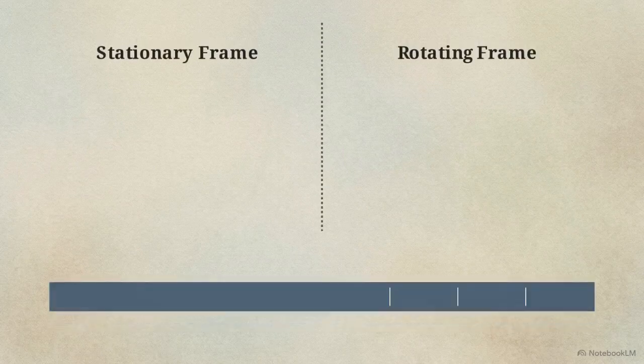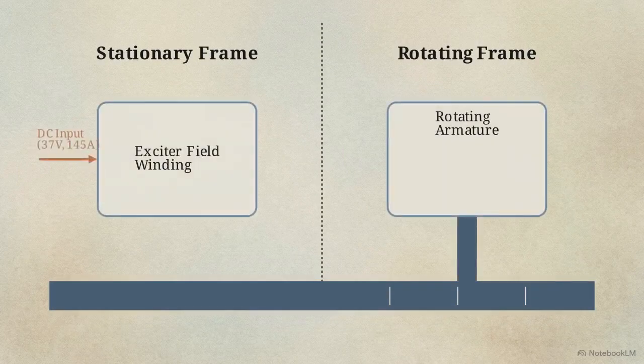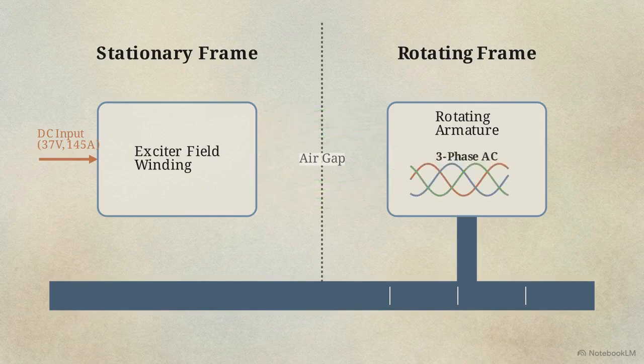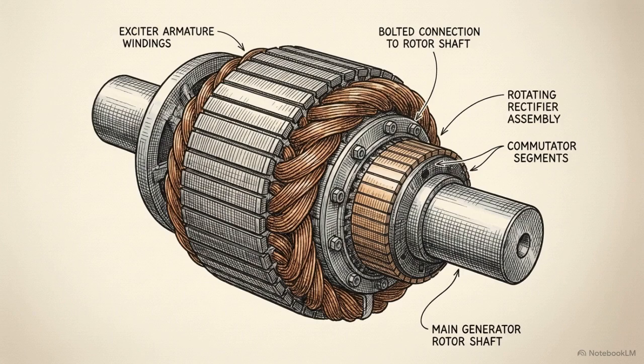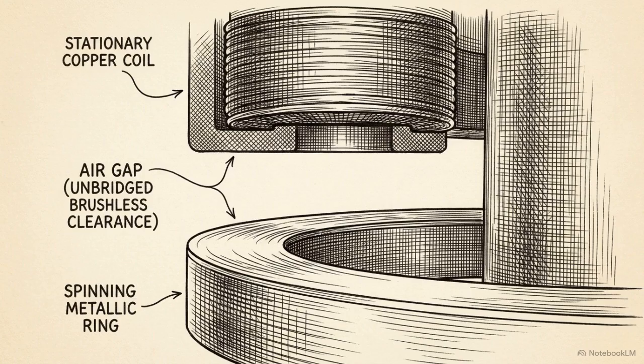This split-screen diagram maps the brushless excitation scheme using an inverted alternating current synchronous generator coupled to the main shaft. First, DC power feeds into the exciter's stationary field winding, inducing an alternating current across the gap into the rotating armature. By putting the armature on the spinning shaft, the three-phase AC power is generated natively within the rotating reference frame. There is no need to bridge the gap with physical contacts.